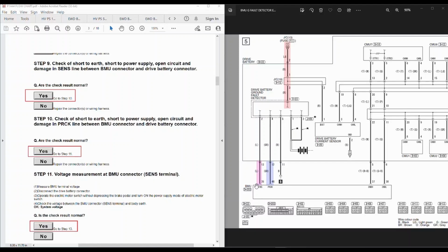What I did do is I left this connector disconnected from the BMU, but left it connected inside the battery here, just to see if I could get any indication of a short circuit inside the battery. So in other words, rather than disconnecting here and just having a free length of cable, I disconnected from here and left it connected to the battery. So then I could see if there was anything internal. There were values, I think 7.8 kilohms on one of them, sorry. There was no real specification for that. It was just to say that we hadn't got a short inside there. That was the best we could do with that situation.